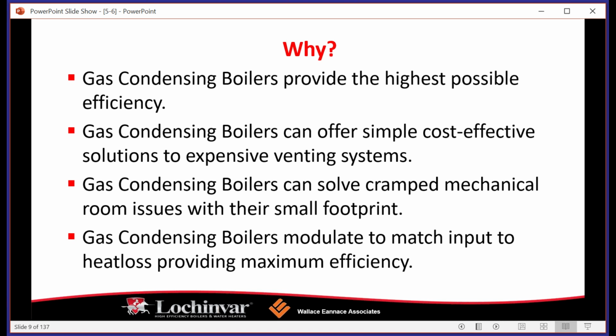So when we discuss the Lochinvar products, when they're installed and they're running the way that they're supposed to, you can get up to 99% efficiency. You know, so say 90, 95%, you take that same dollar, and what you're going to see is that 95 cents of your dollar is used as energy, right? It's used to heat the house or the space. 5 cents of your dollar is flue gases, right? We're never going to get to 100% efficiency, but we can get very close. So the advantages are that if you're taking an older piece of equipment and you're replacing with a condensing piece of equipment, you're going to see significant, very significant fuel economy improvements, which translate directly to dollars saved and returns on investments.